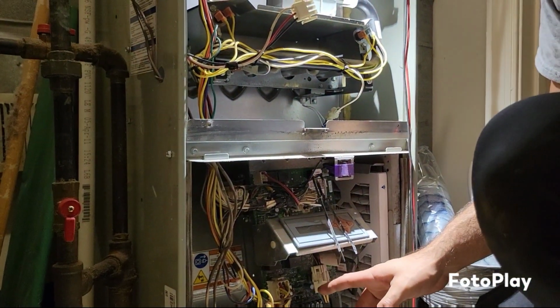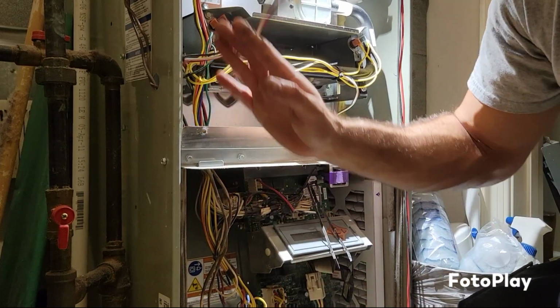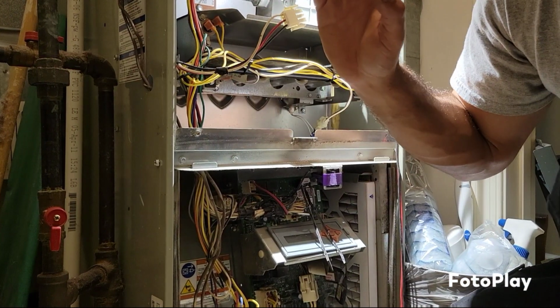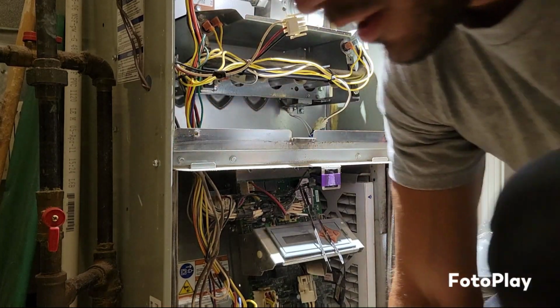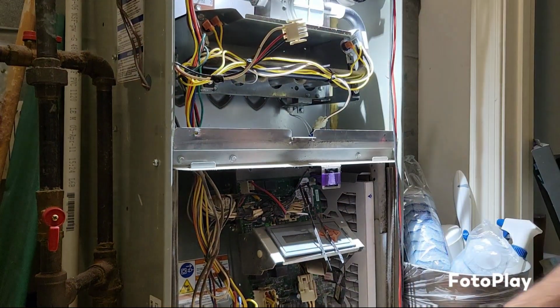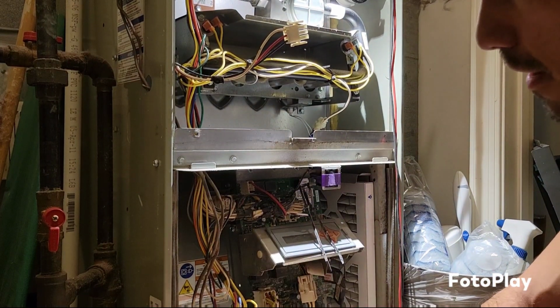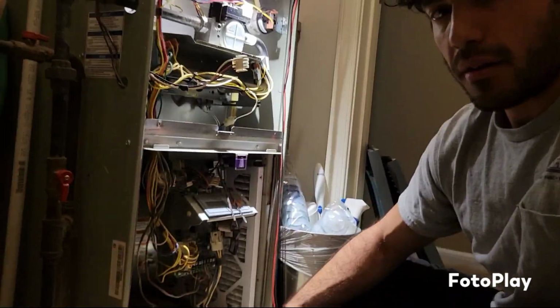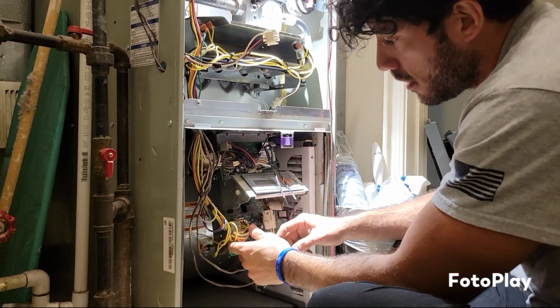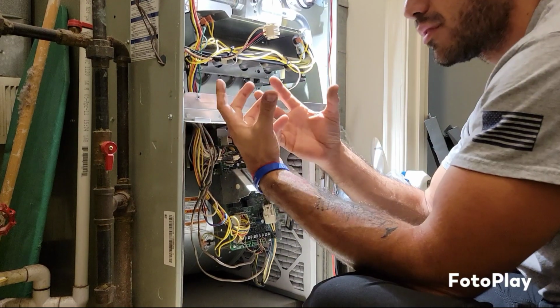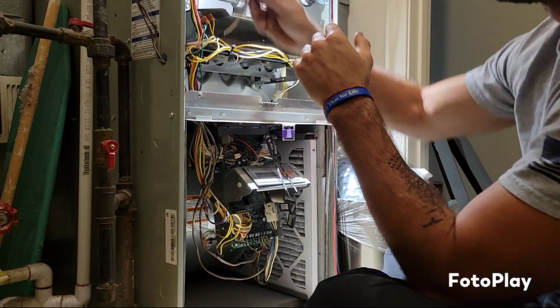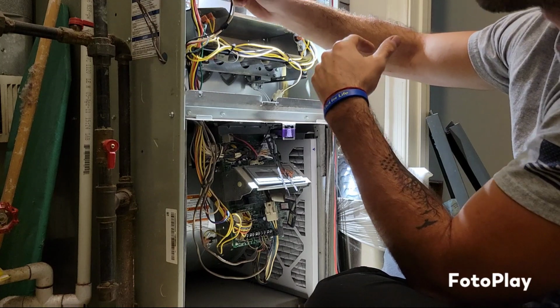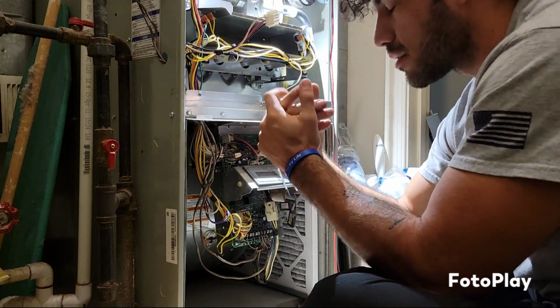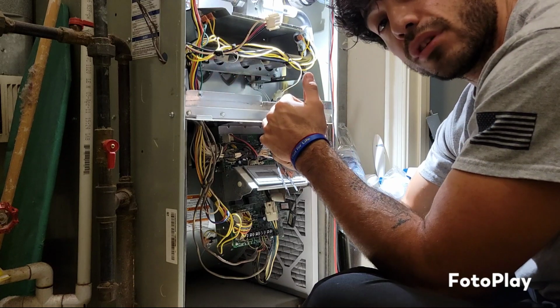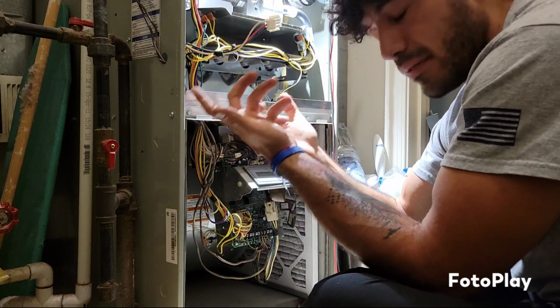So down here, in this board right here, we're not getting the power that we need up to the actual motor. So the issue here is not necessarily the fan motor, even though that's what the error code is calling for. Like, hey, we have a pressure switch error code and my fan's not spinning. But the issue is more over here in this board. So when the relays close, to get the voltage transferred up here to this motor, we either have a relay that is not closing or stuck, or something's going on where we're not transferring the correct voltage to the right application that we need to run.